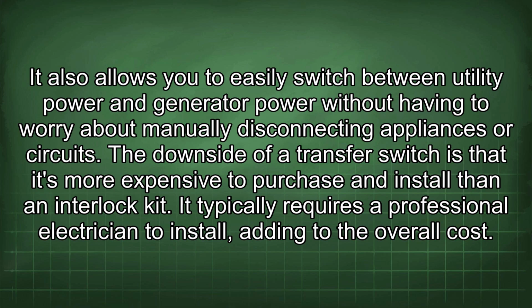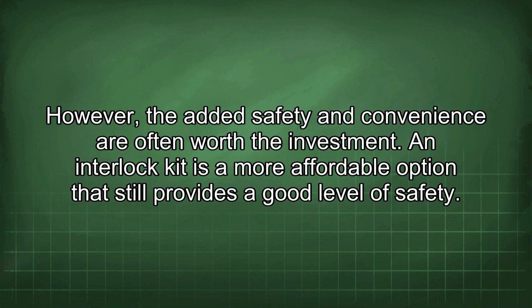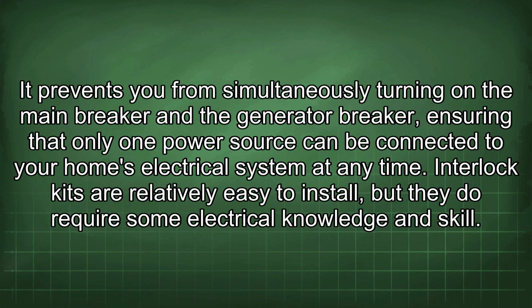The downside of a transfer switch is that it's more expensive to purchase and install than an interlock kit. It typically requires a professional electrician to install, adding to the overall cost. However, the added safety and convenience are often worth the investment. An interlock kit is a more affordable option that still provides a good level of safety. It prevents you from simultaneously turning on the main breaker and the generator breaker, ensuring that only one power source can be connected to your home's electrical system at any time.